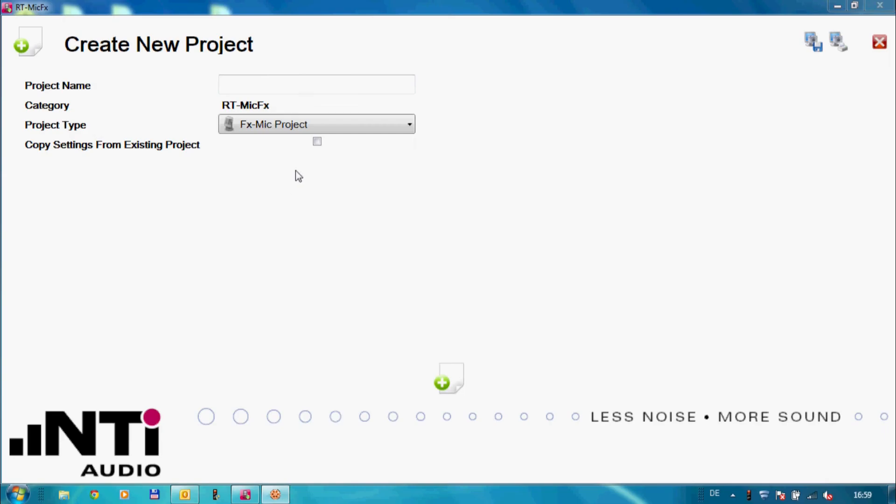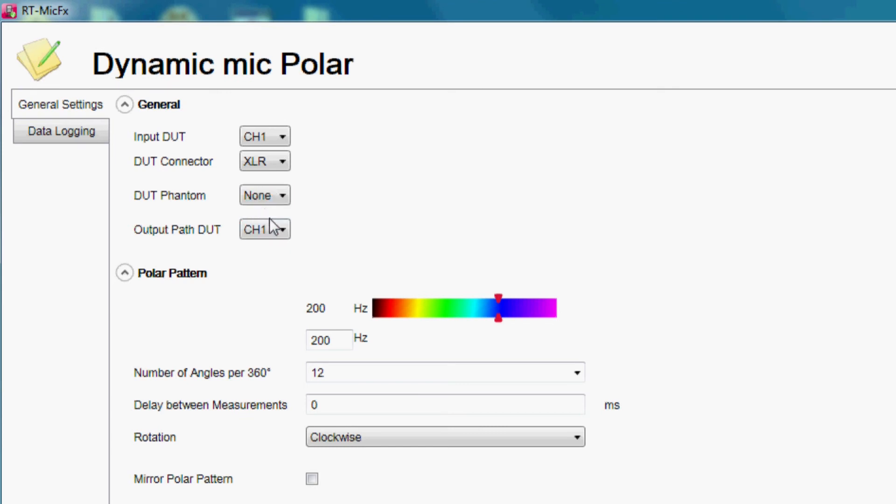When we select the microphone directivity option, the system can also produce polar plots by using a turntable. The setup is very easy. We define the number of measurements during the 360 degree rotation and the rotation direction.